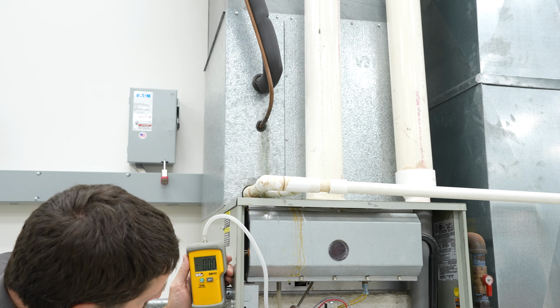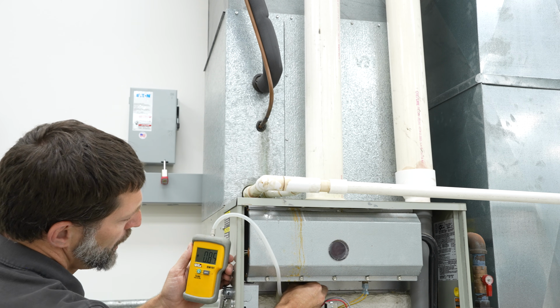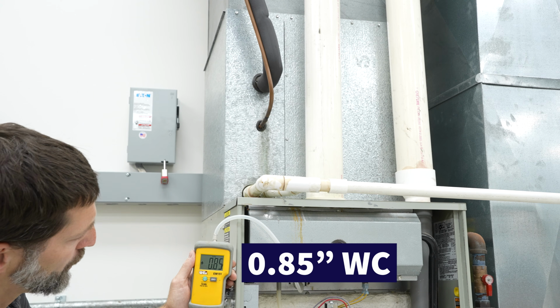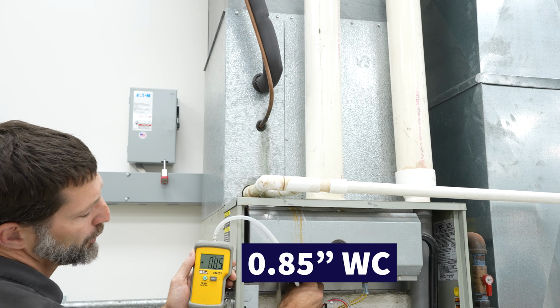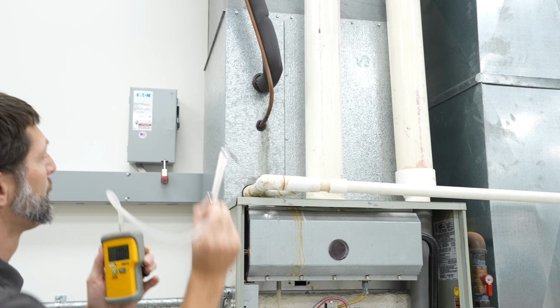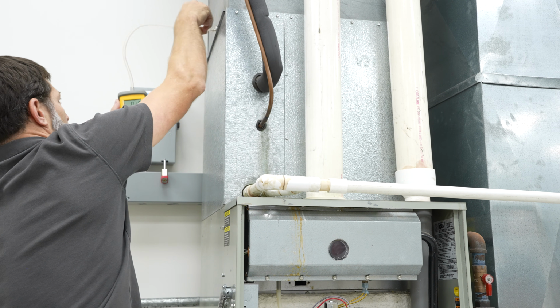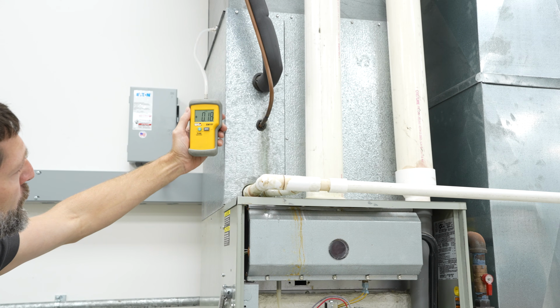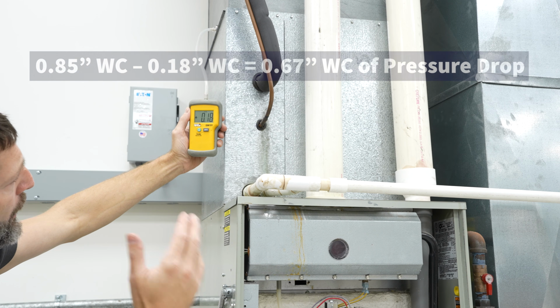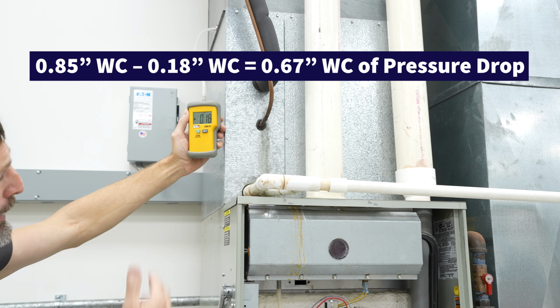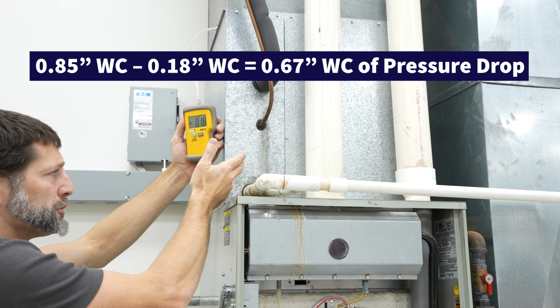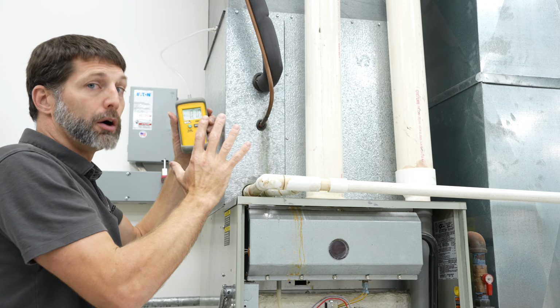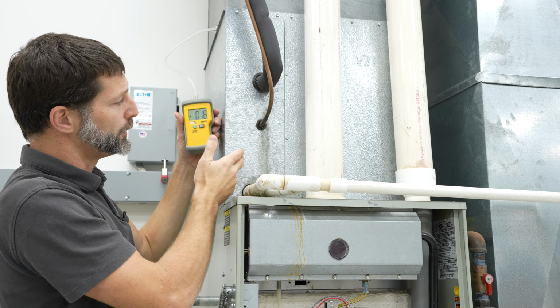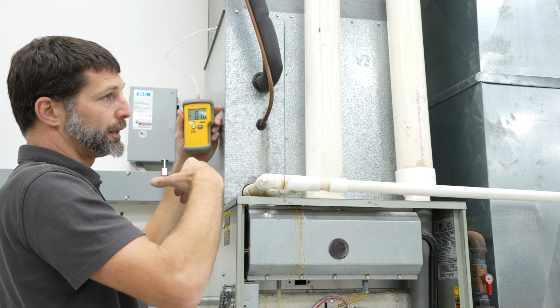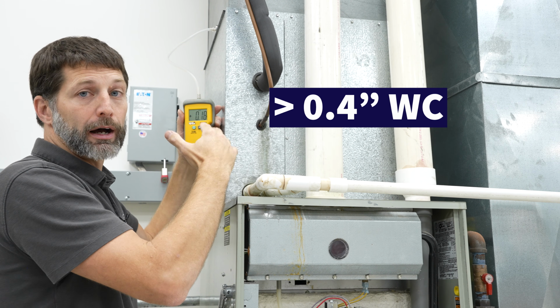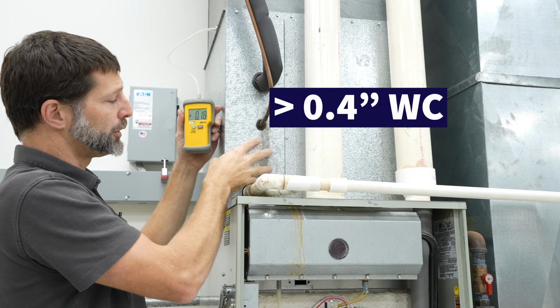You don't need a 2-port digital manometer in order to do this, so you can just use a single port. You can take your measurement here, which is 0.85, and you take your second measurement here, which is 0.18, so you get 0.85 minus 0.18, and you have your same pressure drop across this coil. So you know for sure that this coil is clogged because you have more than, say, 0.4 or 0.5 inches of water column pressure drop across here.